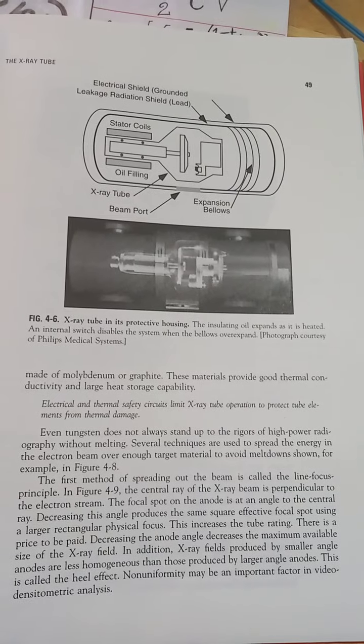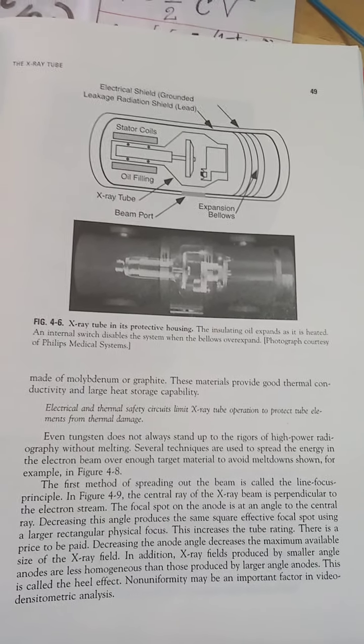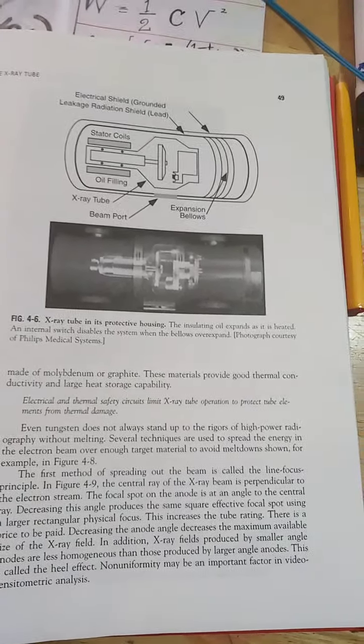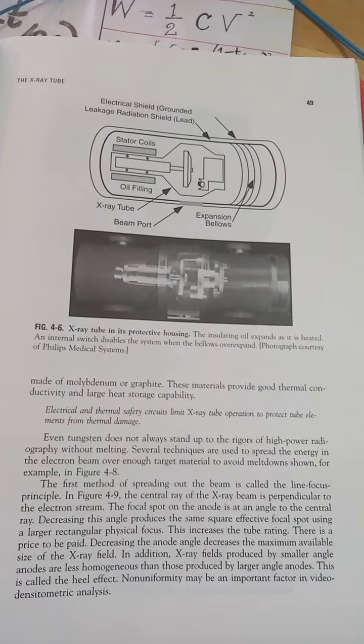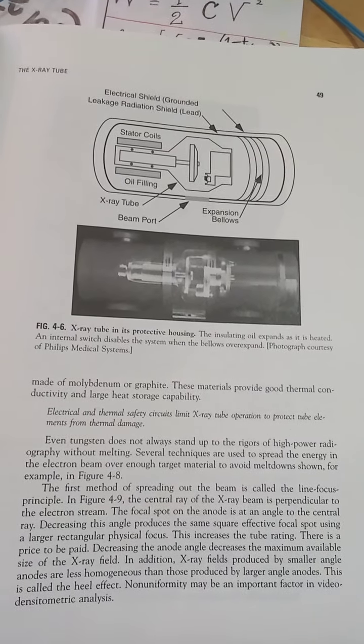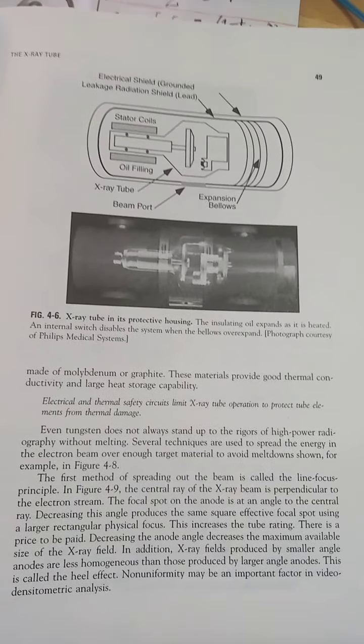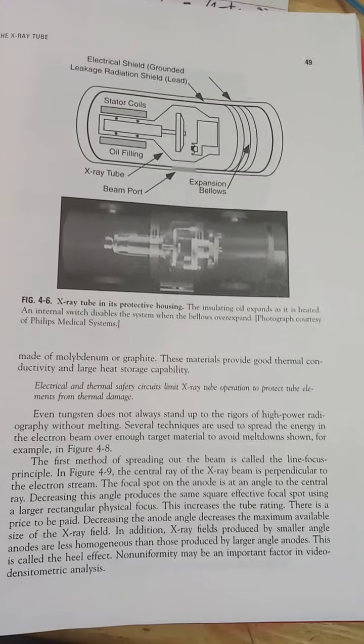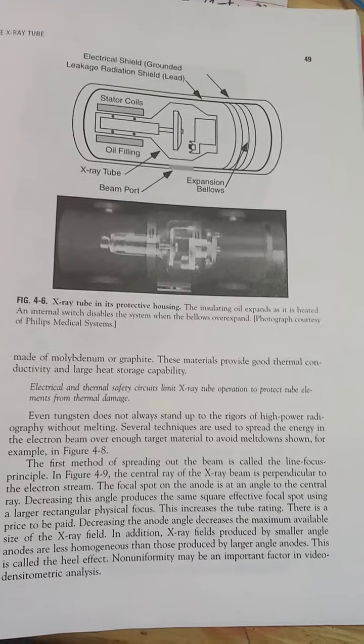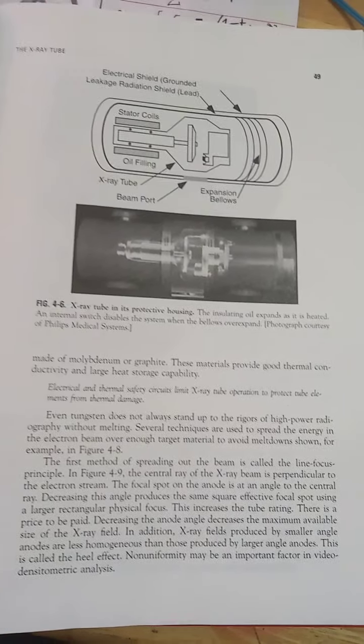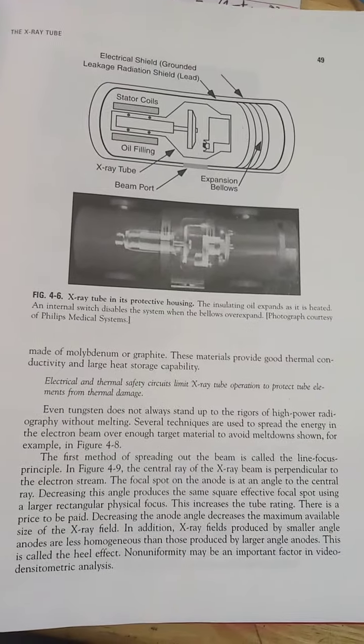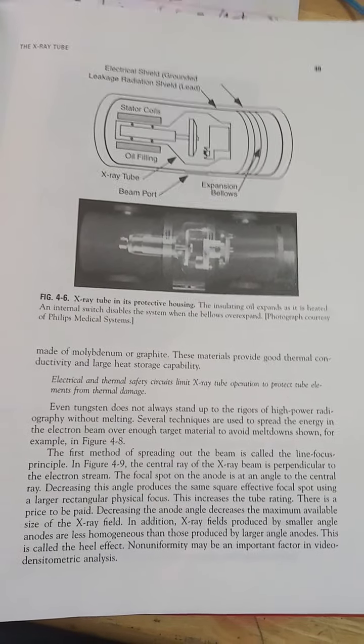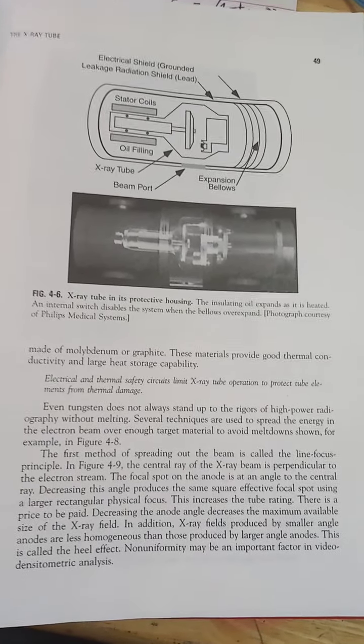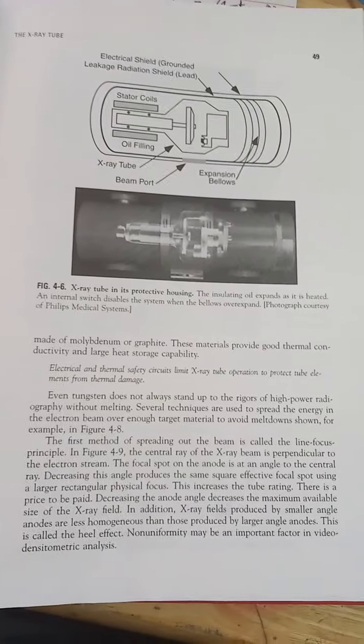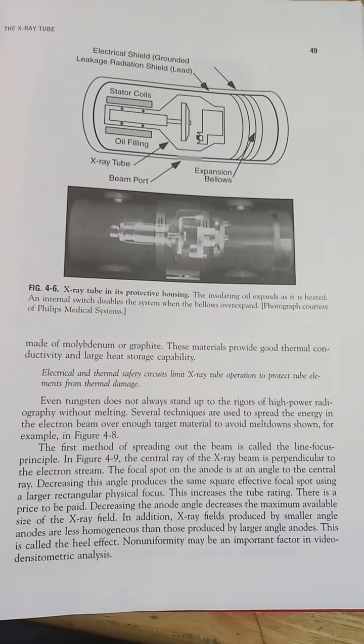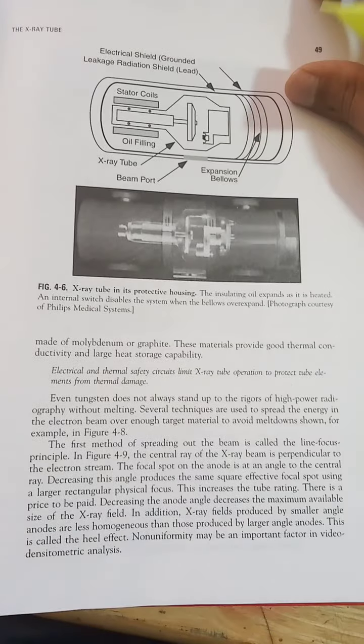This is obviously a trade-off where the quality suffers, and decreasing the anode angle decreases the maximum available size of the X-ray field. In addition, the X-ray fields produced by smaller angle anodes are less homogeneous than those produced by larger angle anodes normally. This is not normally in the sense of perpendicular, but normally as in the convention. This is called the Heel effect. Non-uniformity may be an important factor in video densitometric analysis.